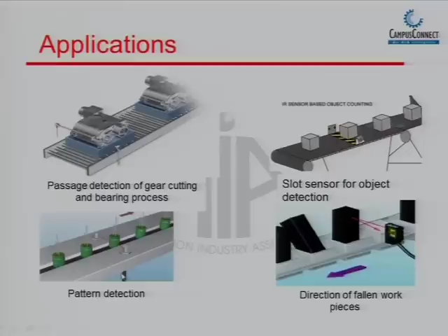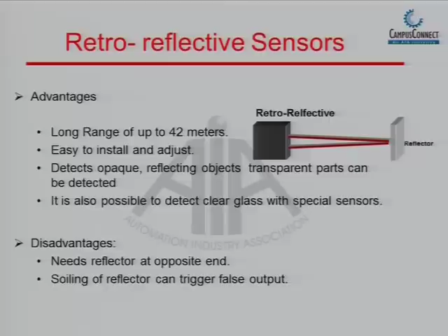Then retroreflective sensors, as I said, require a reflector. The maximum distance you can go up to is 42 meters. The only drawback is if the reflector becomes dirty or soiled, you will still get an output. That means it will sense that there is something in between, as the reflector is not reflecting the light. That means you need to clean the reflector every time. Then again I will just show you a quick video about this.